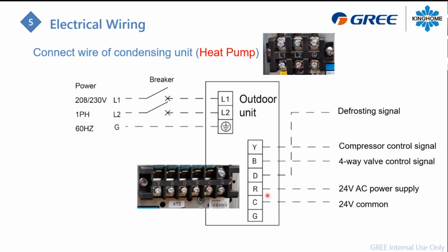So you have your Y terminal. This one will control the compressor signal. You have a B terminal right here. This activates your four-way valve in the heating mode. So you need to configure your thermostat to be active in heating mode while talking about the four-way valve.